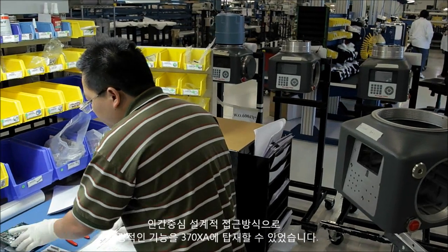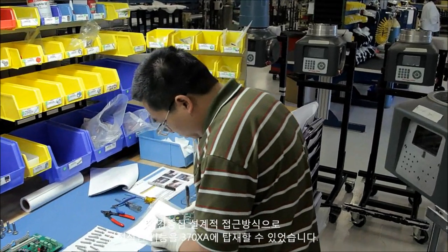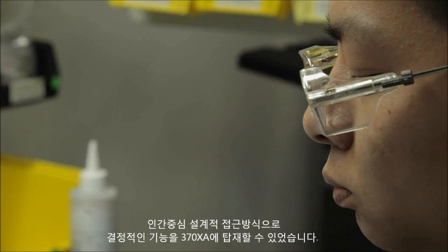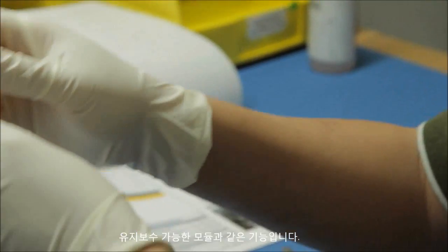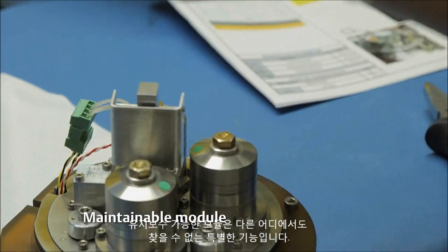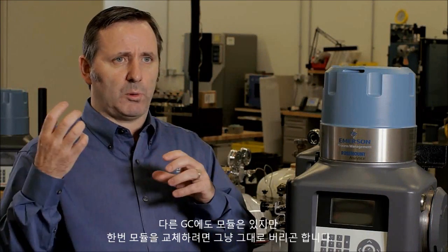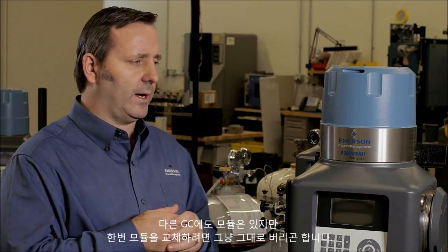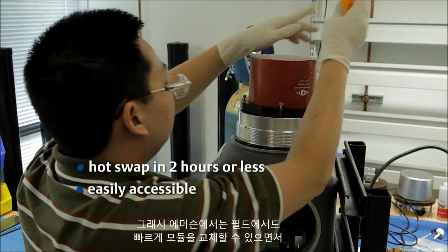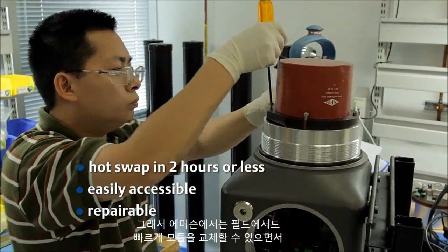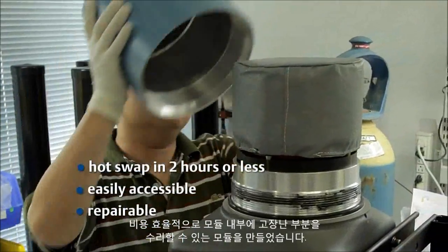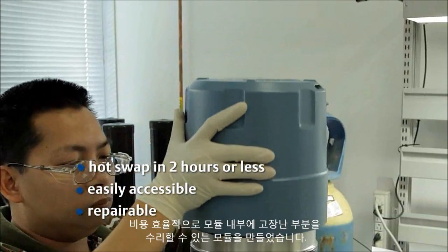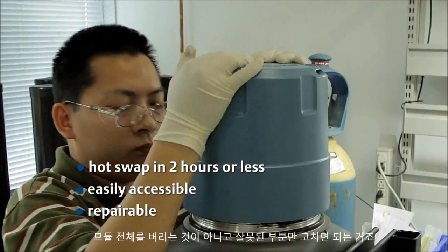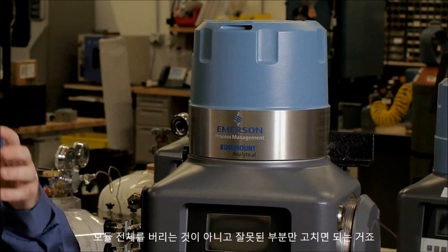The human-centered design approach led us to several key usability features on the 370XA, like this game changer, the maintainable module. The maintainable module is so unique—there's nothing else out there like it. Other GCs have a module, but once it's replaced, that module just gets thrown away. What we've done is build a module we can replace quickly in the field, but cost effectively repair what's broken rather than throw everything out. You're just repairing what's gone wrong.